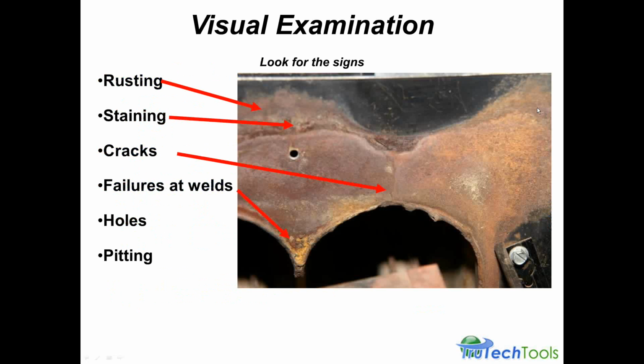So in the visual exam for the heat exchanger, you look for rusting, staining, cracks, as illustrated in this photograph, failures at the weld, holes, pitting. And one comment here is many times the heat exchanger issues are not related to poor heat exchanger design, but more related to either maintenance or installation. If there's insufficient flow over the heat exchanger, the flame's not going to be in the right place, burning with the right intensity, perhaps overheating the metals in the heat exchanger, or if there's excessive fuel pressure, which causes too long of a flame, again, the flame being in the wrong place at the wrong time. So these are why the manufacturers have specific setup parameters for airflow and for fuel pressure to make sure that the components don't get degraded by poor installation or poor maintenance.